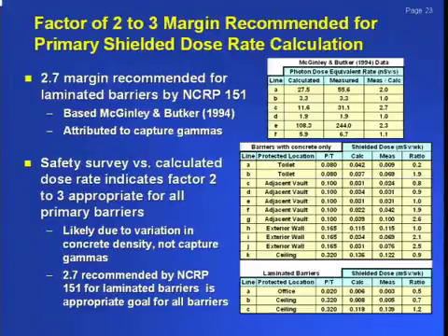And so am I safe and comfortable in saying yes, if you have to make a calculation for a truly minimum barrier, if you use this method, you will be okay. It's just that when you do your safety surveys, you will come out right at the limit.